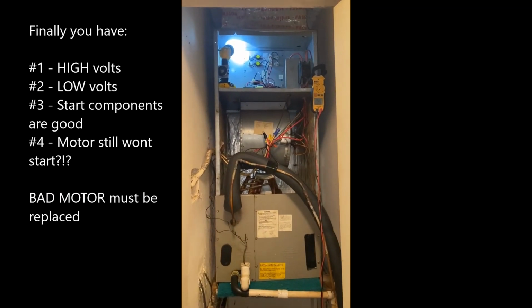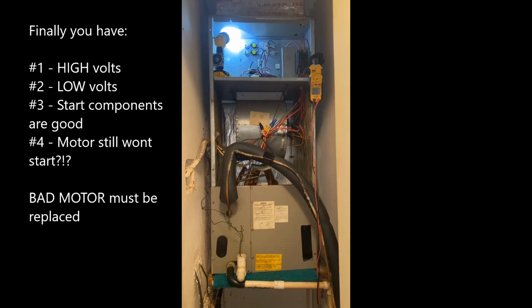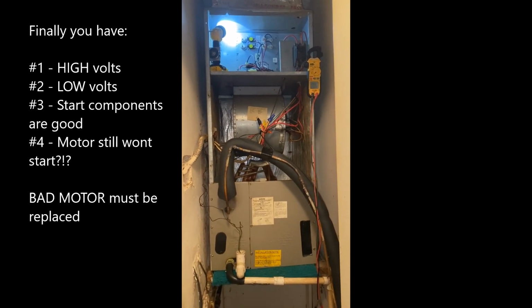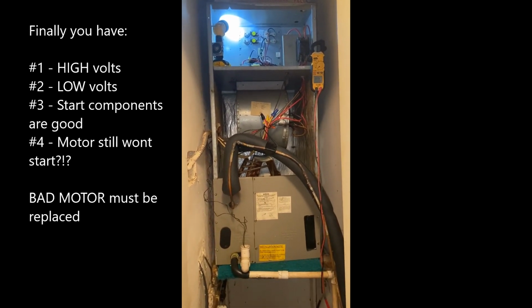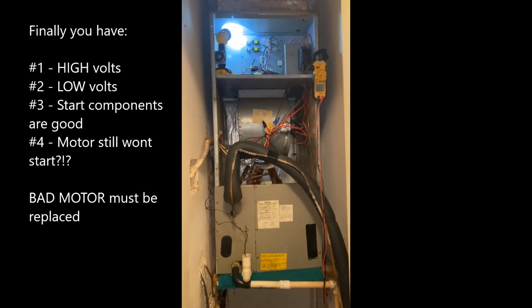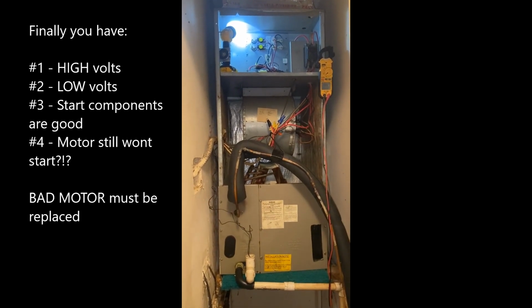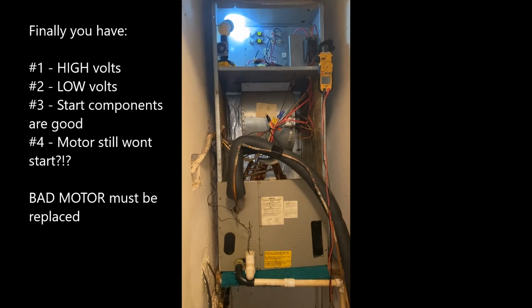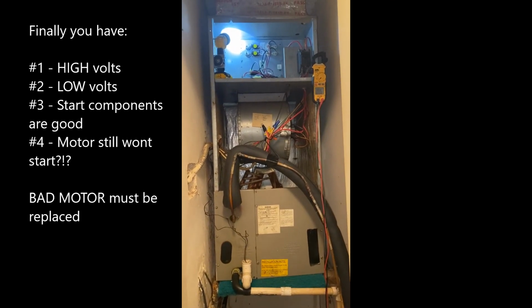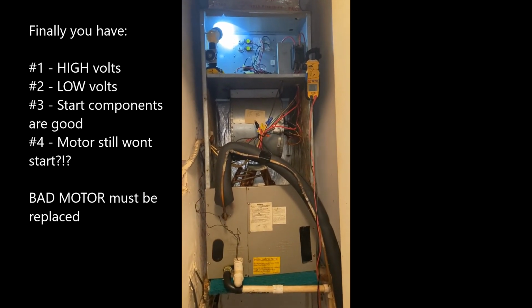So finally, we have high voltage, low voltage. Our thermostat is calling our relay. Power's getting to the motor. The capacitor is good, but that fan still doesn't run. You've got to replace the motor. That motor's bad. Check out my video on replacing evap motors.